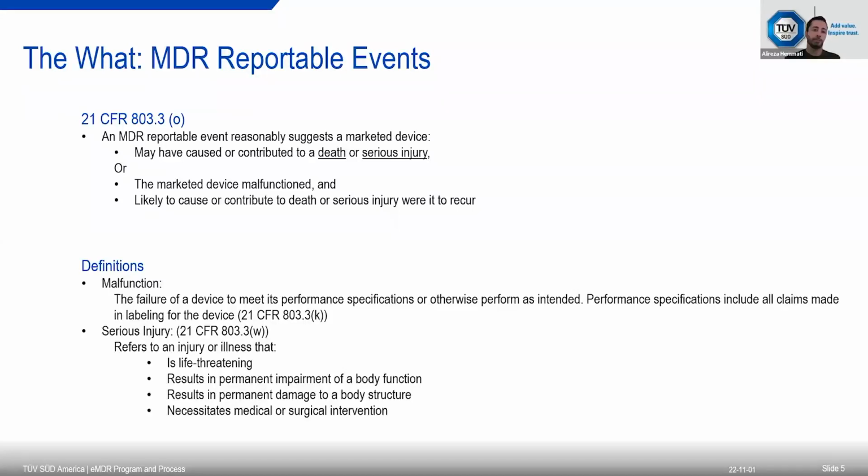Based on 21 CFR 803, an MDR reportable event is an event that reasonably suggests a marketed device either may have caused or contributed to a death or a serious injury, or that the marketed device malfunctioned and it's likely to cause or contribute to death or serious injury were it to occur again.